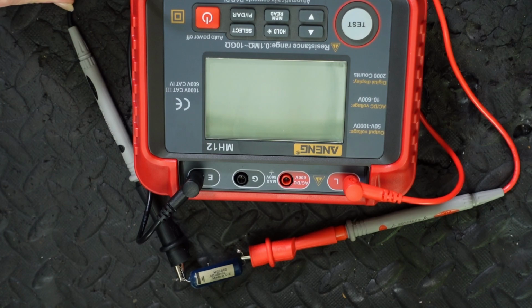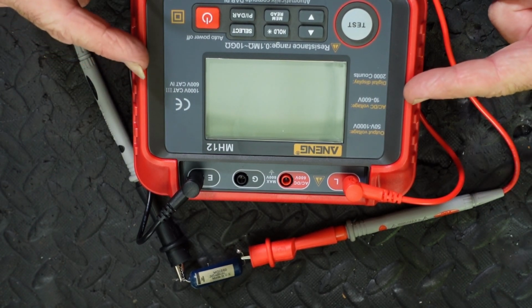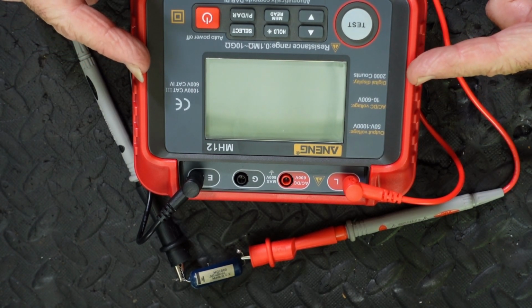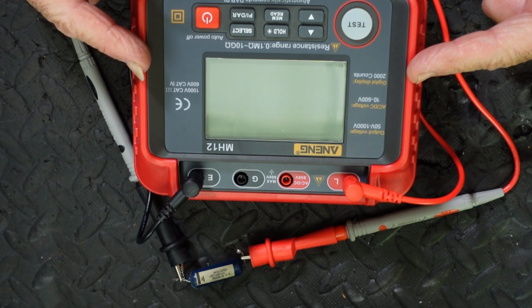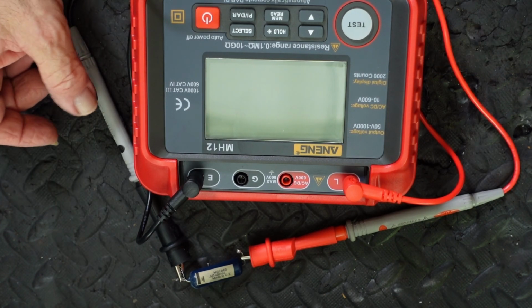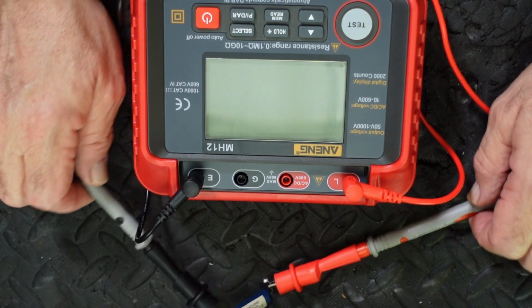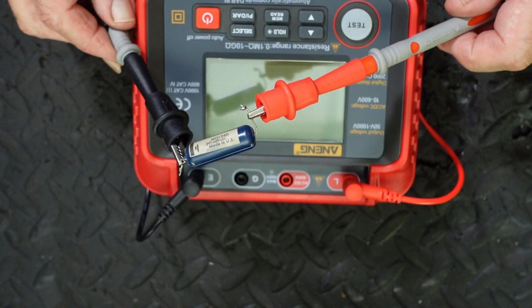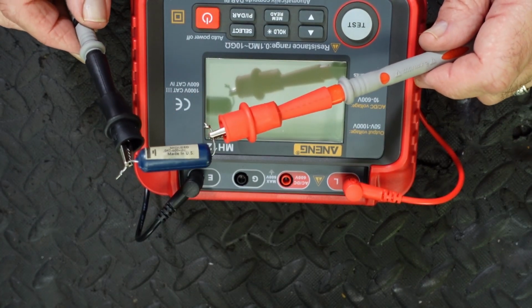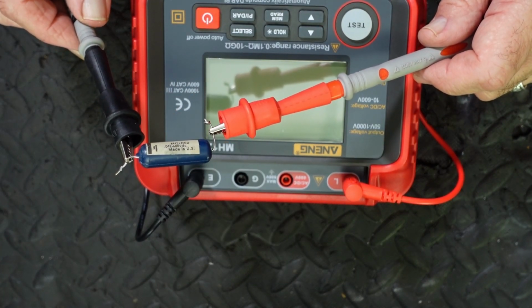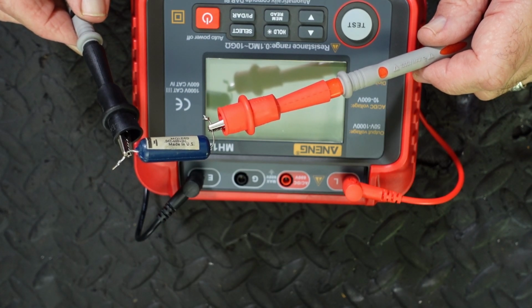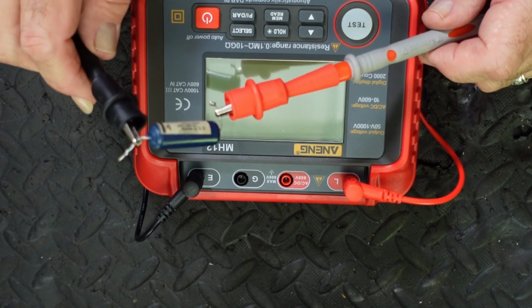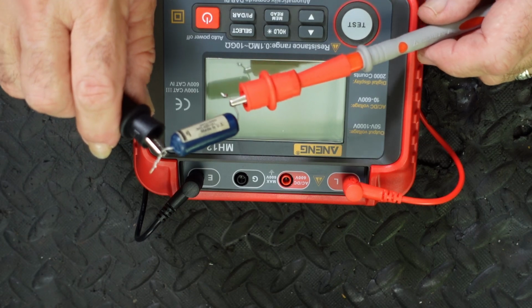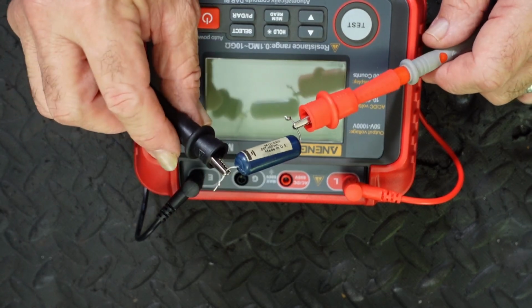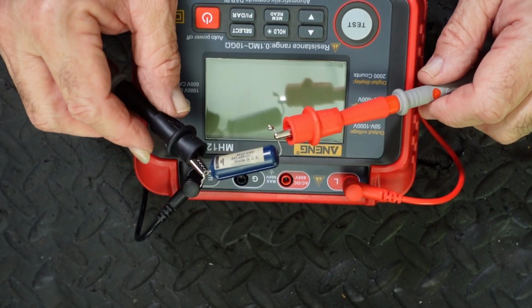So I'm going to prove a point here. Do you know what a mega is? A megger is used for testing megaohms, generally for things like insulation. But we're going to use it to see if these vintage caps, and this one would be at least 60 years old, leak under high voltage. And I'm thinking it's not. So why were they all replaced? My best guess is theft or total incompetence. So we're going to prove it.